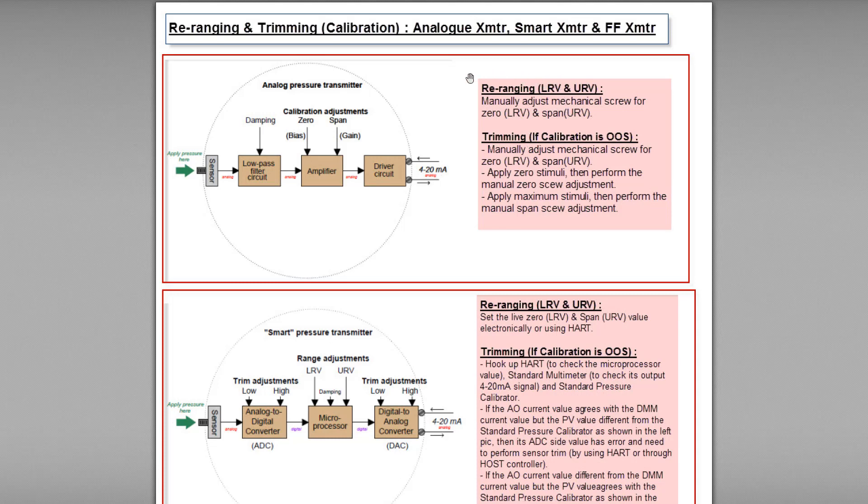If we want to do the re-ranging, we have to adjust the zero and span screws, usually located on the transmitter output terminal side. The zero screw can also be called the bias screw, while the span screw can be called the gain screw. The zero screw can be referred to as LRV — low range value — and the span screw as URV, or upper range value.